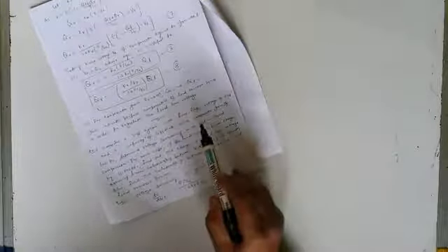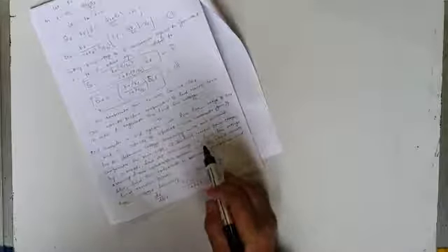Here is the example. It says: consider a three-phase system with line-to-line voltage of 11 kV and short circuit capacity of 480 MVA with compensator gain of 100 per unit. Determine voltage sensitivity with and without compensator. For each case, if the load reactive power changes by 10 MVAr, find out the change in load bus voltage assuming linear relationship between V and Q, that is, VQ characteristics are linear. Also find the relationship between compensator and load reactive power. This is a very interesting problem.